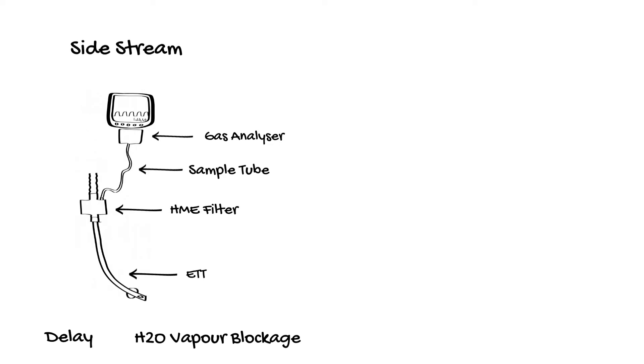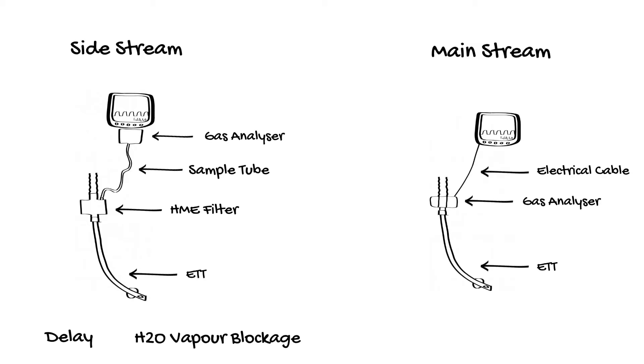Main stream analysers require the sampling chamber to be in close proximity to the endotracheal tube. This makes it bulky at the patient end but dramatically reduces the reaction time of the monitor. Main stream analysers are heated to above body temperature to prevent the window from fogging. On early generations, this could cause skin burns with prolonged patient contact but this doesn't occur with later generations.